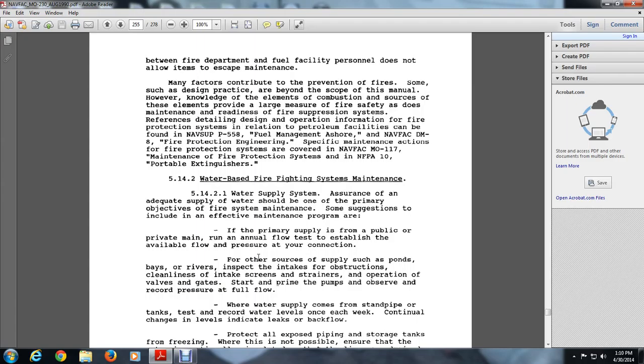5.14.2 Water-based firefighting system maintenance. 5.14.2.1 Water supply system. Assurance of adequate supplies of water must be one of the primary objectives of fire system maintenance. Some suggestions for an effective maintenance program are: ensure the proper supply of the public and private mains and run an annual flow test to establish available flow and pressure at the connection, or other sources of supply such as ponds, bays, and rivers. Inspect intakes for obstruction, clean intakes and screens, and exercise operational valves and gates. Start the primary pumps and observe and record pressures at full flow.